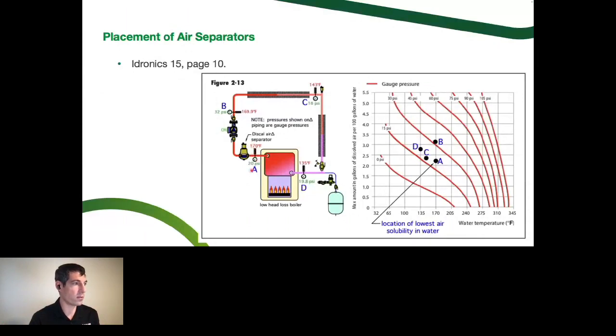They've come out of solution, and it's a low enough pressure that we can get that right out at the top of the air separator there. If we were to put that same air separator at position B, we've just boosted the pressure with the circulator up to 32 psi in this example. Even though the temperature's hot, we just forced all those bubbles back into solution.